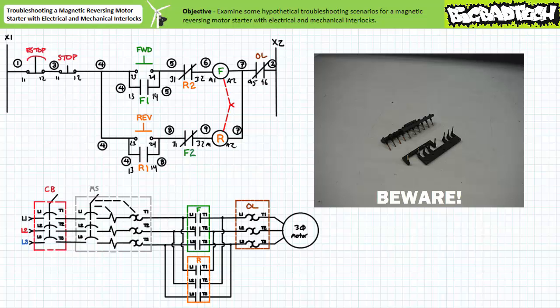Good work practices dictate you properly confirm, inspect, and secure wires, and tighten them to the manufacturer recommended torque specifications. Very often a system passing a superficial visual inspection may necessitate invasive instrumentation inspection to find the particular terminal not making contact. Again, wire numbers are more properly thought of as nodes.